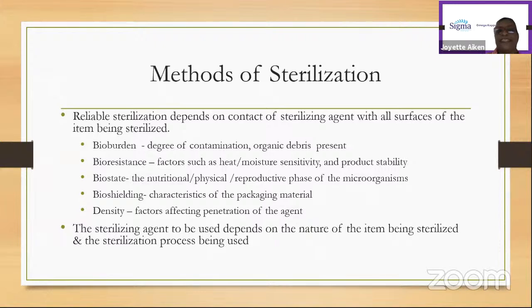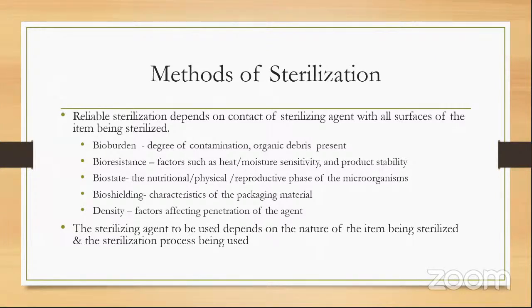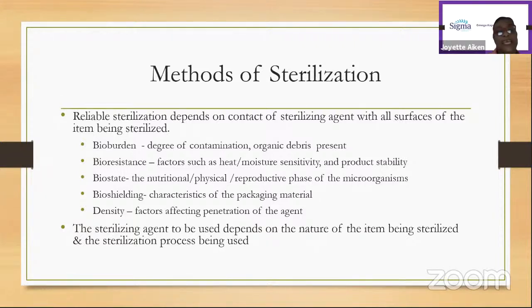So if there is an instrument that has blood or pus on it, you really cannot effectively sterilize that item because there is too much bioburden on it. Remember, part of the guiding principle is that the sterilizing agent must come in contact with all the surfaces of the item being sterilized. So if there is pus or blood on an instrument, then that particular area where the pus or the blood is not coming in contact with the sterilizing agent. So what you will have is sterile pus or sterile blood, but underneath that, there will be contamination there.